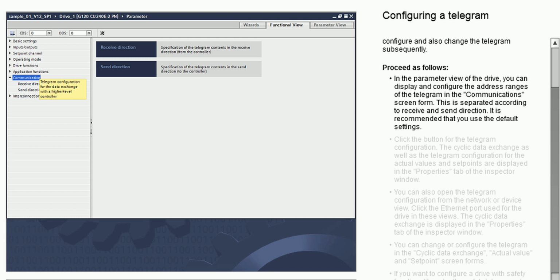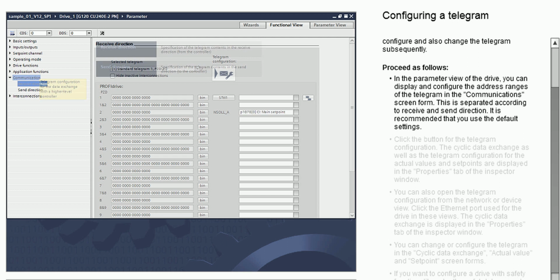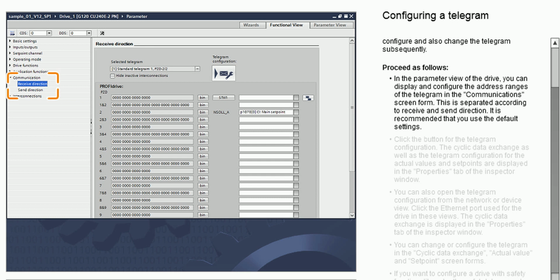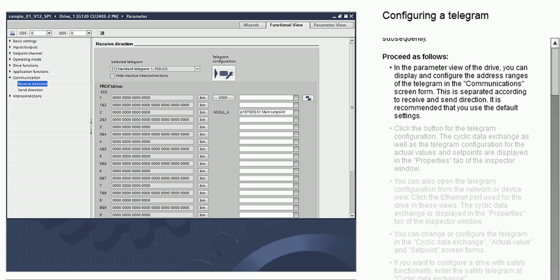Proceed as follows. In the parameter view of the drive, you can display and configure the address ranges of the telegram in the Communications screen form. This is separated according to receive and send direction. It is recommended that you use the default settings. Click the button for the telegram configuration. The cyclic data exchange, as well as the telegram configuration for the actual values and set points, are displayed in the Properties tab of the Inspector window.